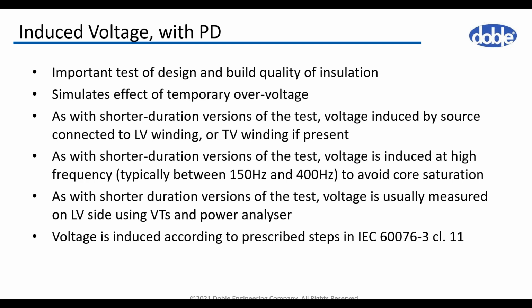The test voltage is applied to the low voltage winding and measured at the low voltage side again using voltage transformer and power analyzer. Here we measure the peak voltage divided by the root of 2, and also we measure the RMS at the same time. As a test voltage, we take the lower value of these two.